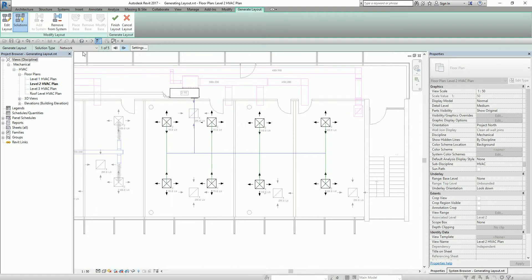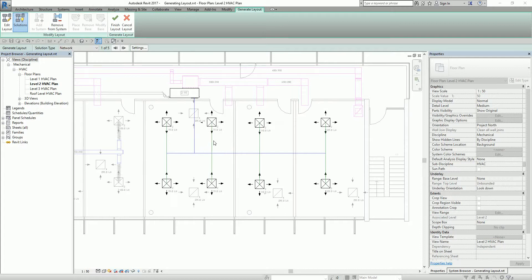The solution type is Network by default. If it is Network, it provides up to six solutions, each consisting of a main segment with branches at 90 degrees from the main segment. The blue lines represent the main duct, and the green color represents the branch duct. Network is the default selection and is most likely to be used in most cases.